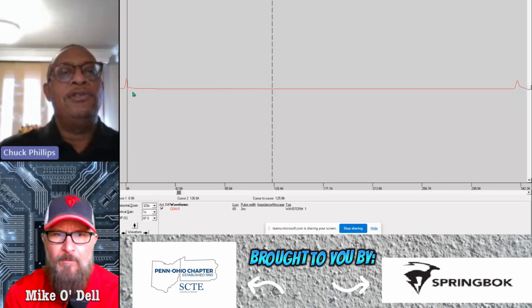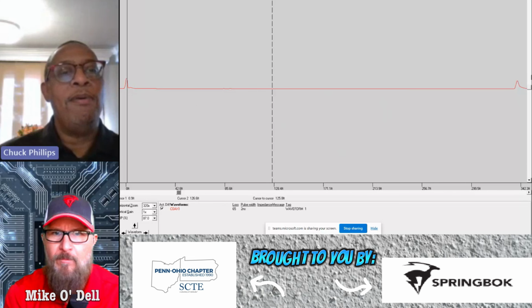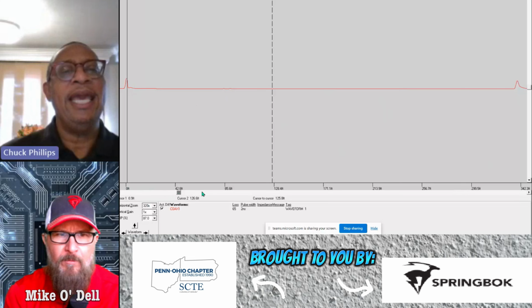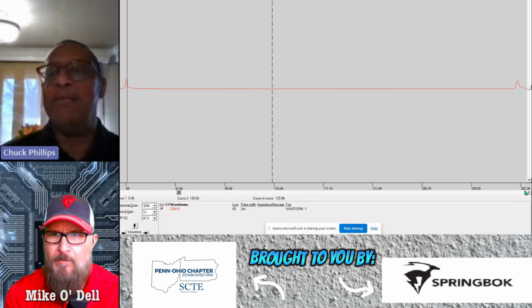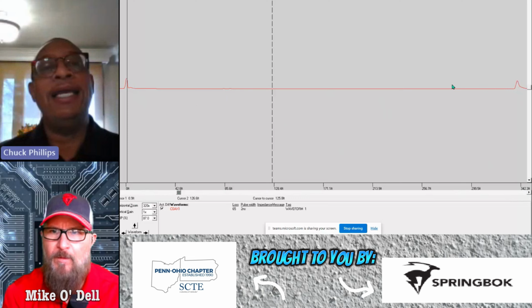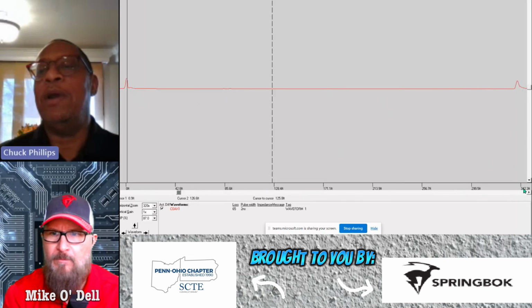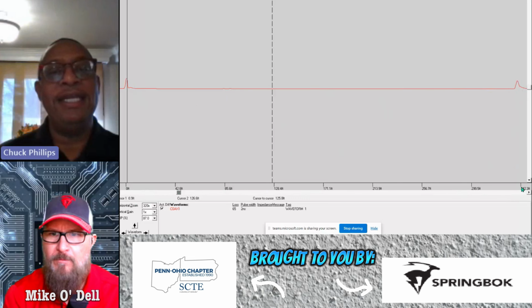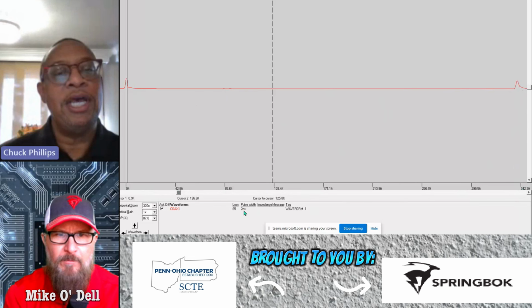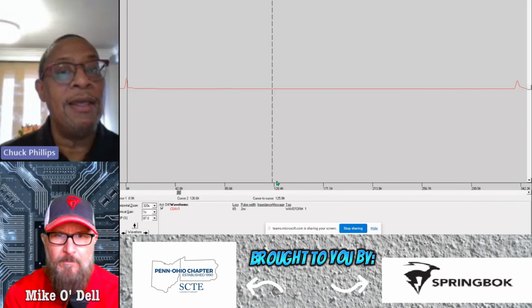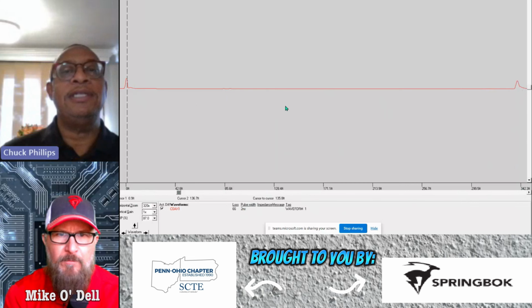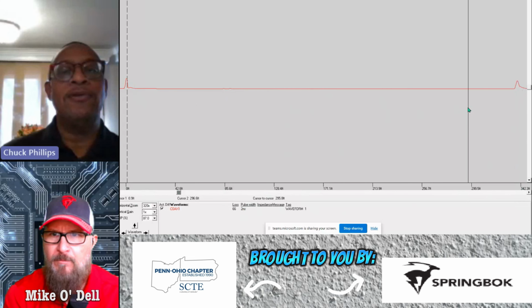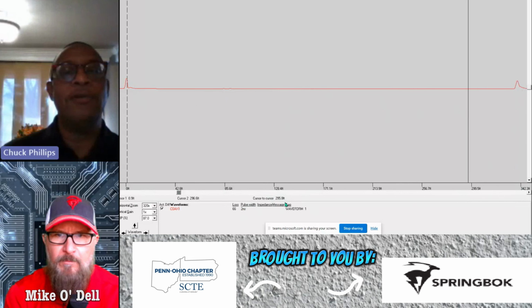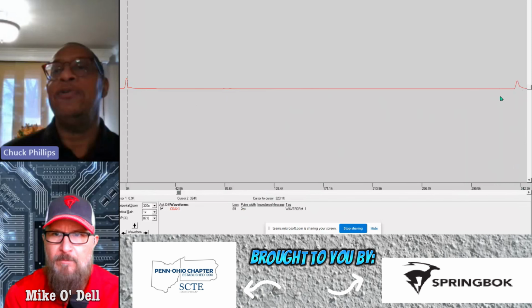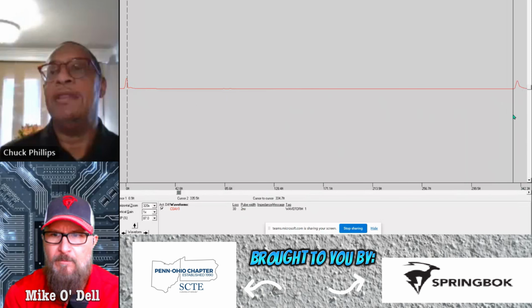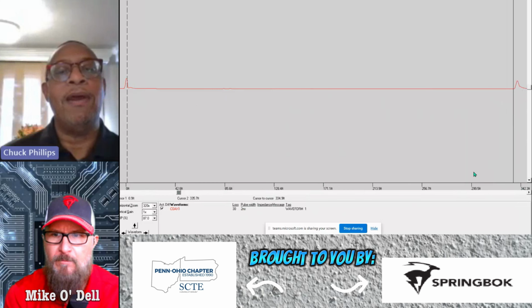Here I have just a regular waveform. A few things I want to point out. I have my scale on the bottom here, which shows me about the footage that I'm looking at. I can see that I have the end of the cable somewhere at about 342 feet. I can see that this was shot in a 2 nanosecond pulse width, but the first thing I want to figure out to see just how long it is, if I move my second cursor right here, you see my cursor to cursor distance change right here.